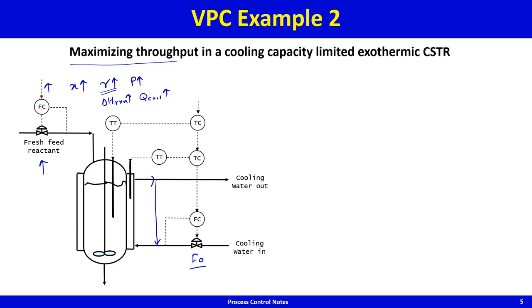We don't want reaction runaway, yet we want the reactor to process as much feed as possible to maximize revenue and plant viability. As an operator, the smart approach is to look at the coolant valve position: if it is only 50% open, you know you can put in more feed.